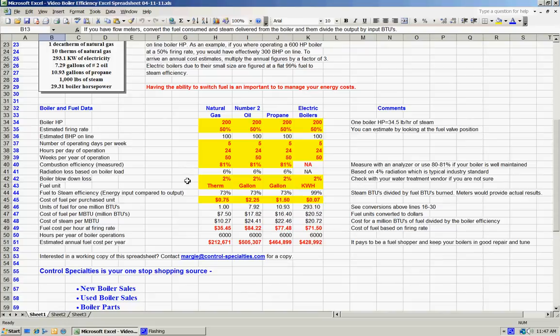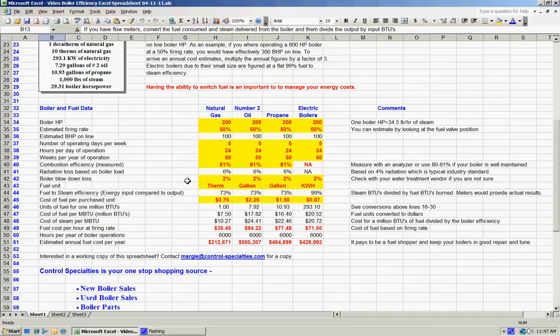Boiler blowdown losses, which is what you're shown in line 42, is going to be essentially a function of your water treatment and water hardness and issues such as that. If you don't know, your water treatment vendor should be able to provide you that information. If not, if you use about 2 to 3 percent for most parts of the country and the water conditions are coming in, you're going to be pretty well straightforward.